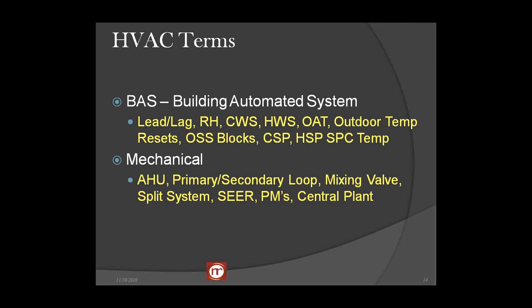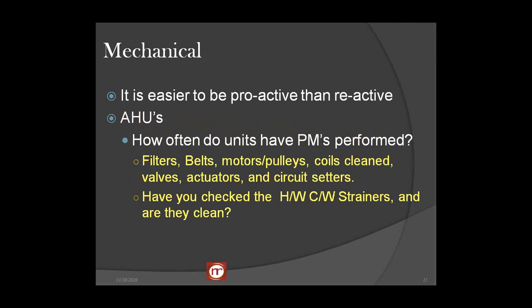Can't tell you how important that is. Central plant is the equipment in the mechanical room, the boilers, the chillers, the pumps. Now, it's easier to be proactive than reactive. And the first question with air handler units is, how often are the PMs performed? And here we're looking at the belts, the motors, the pulleys, cleaning the coils, stroking the valves. And one of the things that's missed the most is the hot water, chill water strainer.